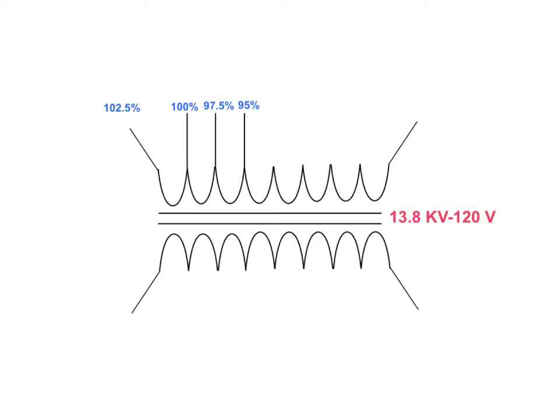Because again, it's winding to winding ratio. Now you notice we have up here 102.5%, 100%, 97.5%, and 95%. Those percentages we're going to apply to our turns ratio. We are not going to apply them to the voltages. It's very common for people to want to apply them to the voltages. We're not going to do that.